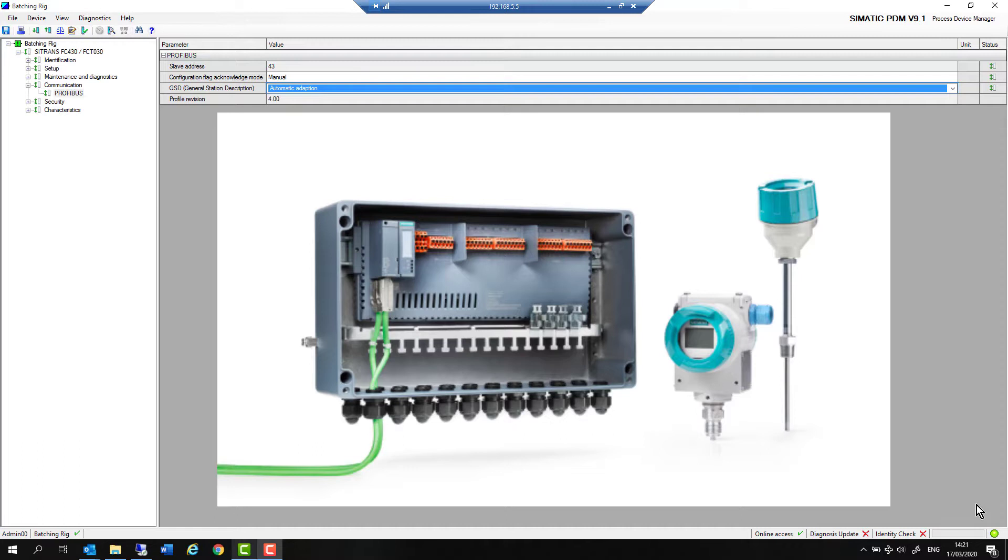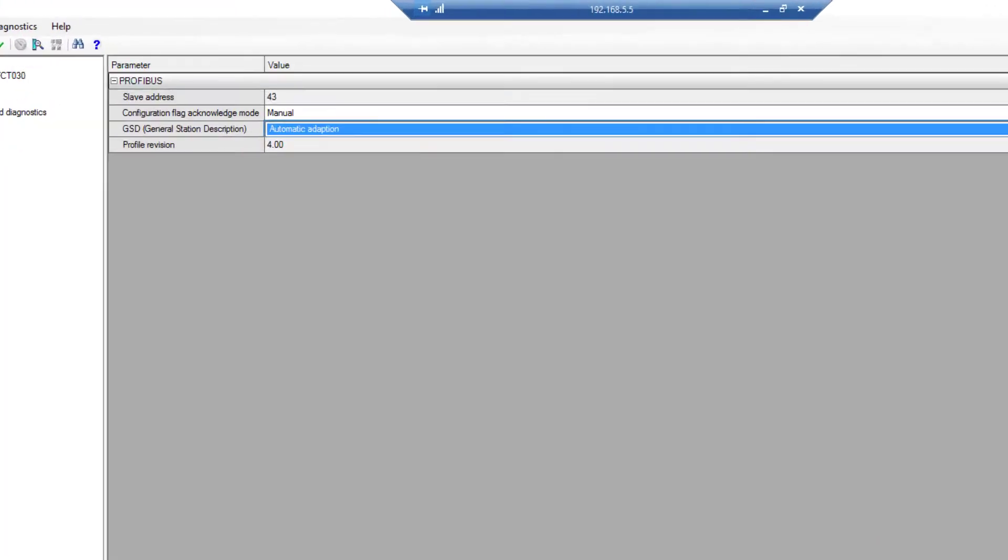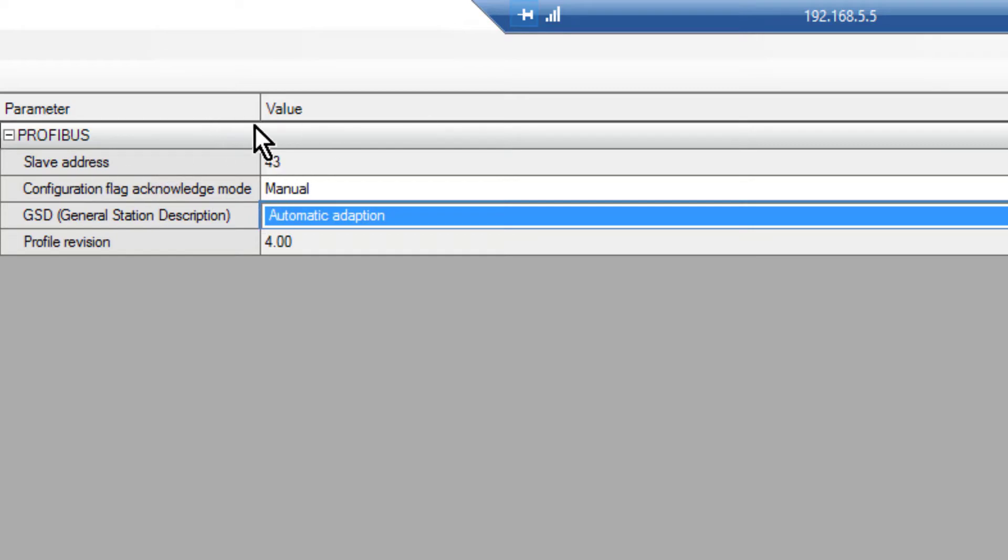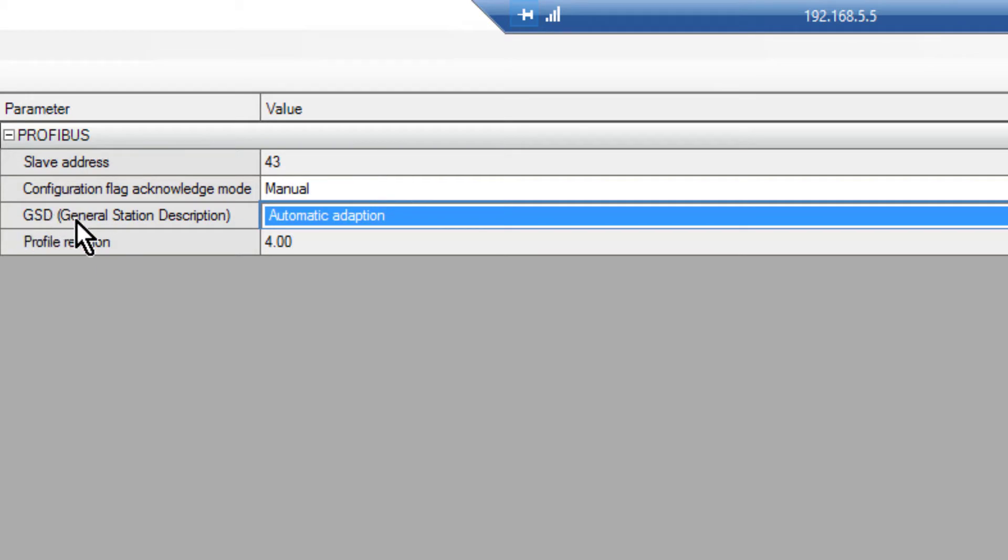Just so you get an understanding about where the instrument sits with regards to GSDs, I have the Coriolis meter from Siemens open here and you can see a slave address list from last time. Because I put the expert code in, I can have a look at this section here. Normally the Compact Field Unit will tell the Coriolis meter what GSD to use.